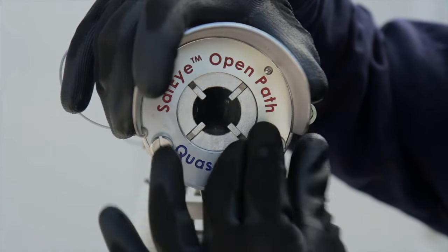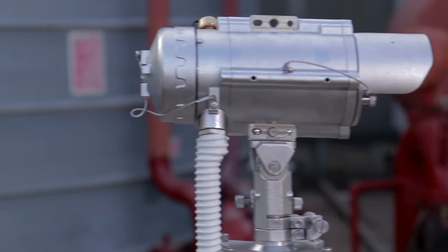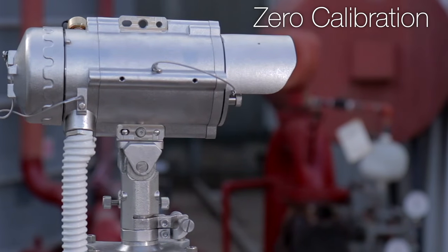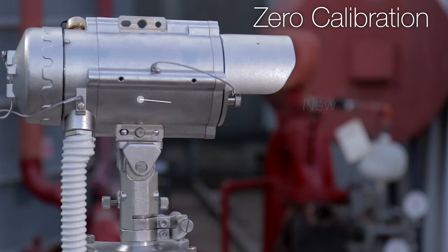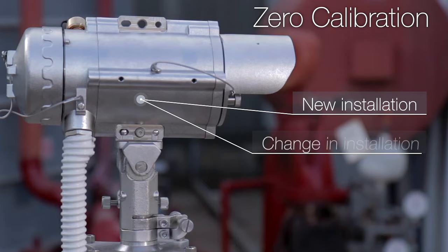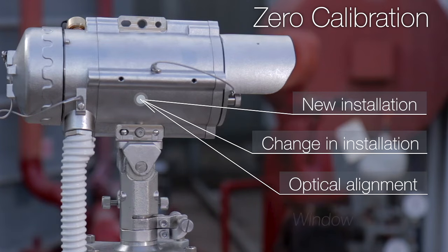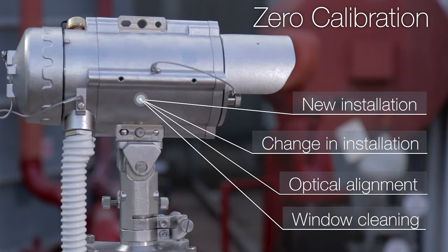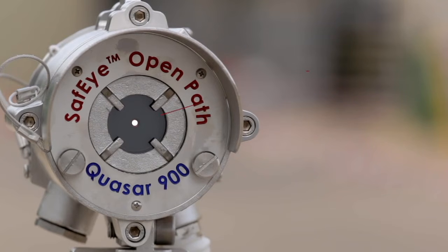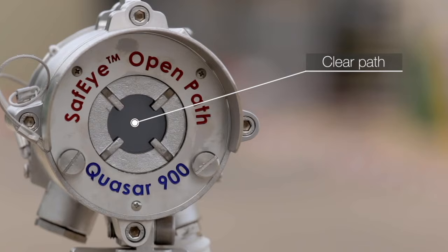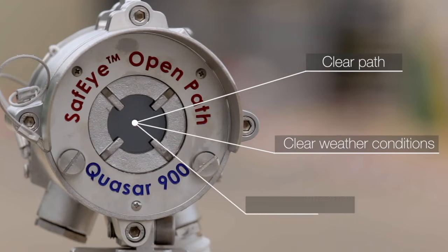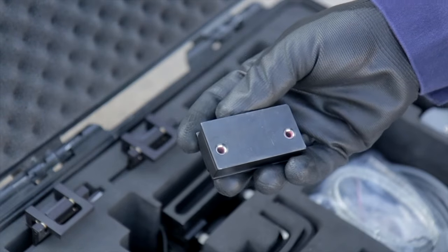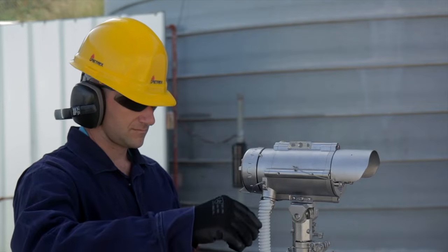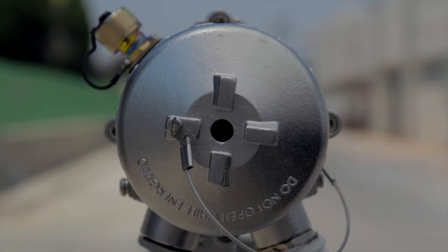The third stage of the alignment is zero calibration. Zero calibration must be done whenever there is a new installation, change in installation, optical alignment, and after window cleaning. Before zero calibration, make sure the path is clear between detector and source. Weather conditions are clear and there is no gas present in the path. To perform a zero calibration, swipe the magnetic mode selector 3 times on the receiver side until the LED turns solid yellow. The system has now begun the zero calibration process.